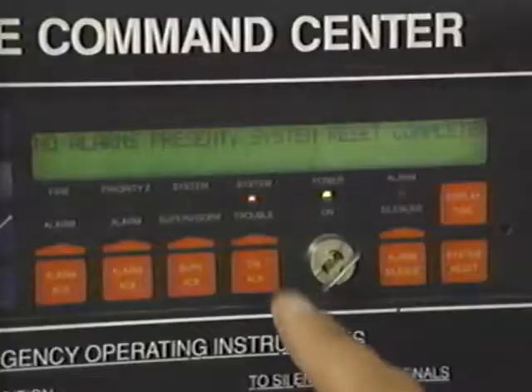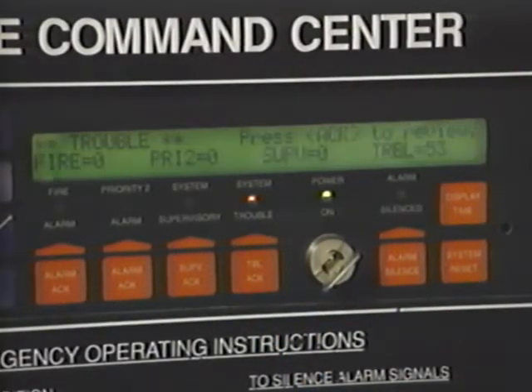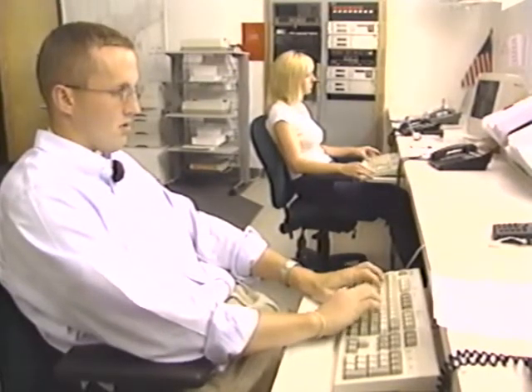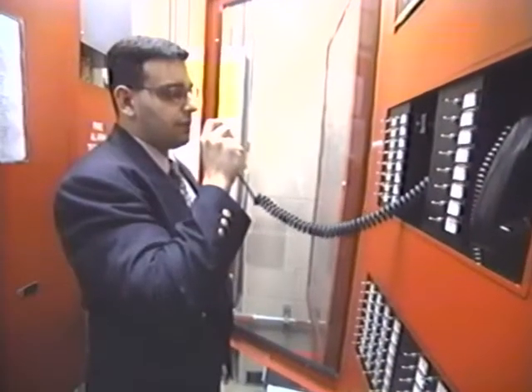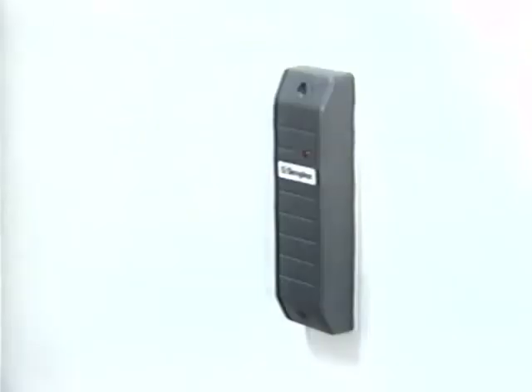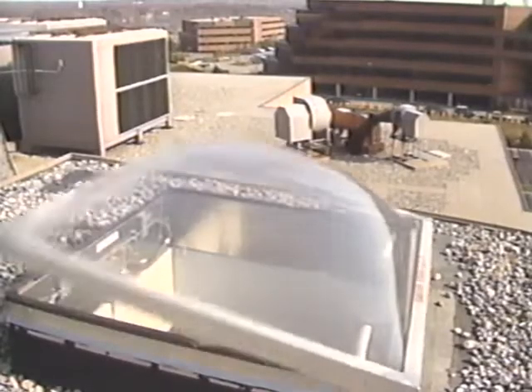Older systems may indicate a zone rather than a specific initiating device. The control unit may also transmit signals off premises, activate local alarm notification appliances, provide voice communication capabilities, activate fire suppression systems, and integrate with other building systems such as door closers and air vents.